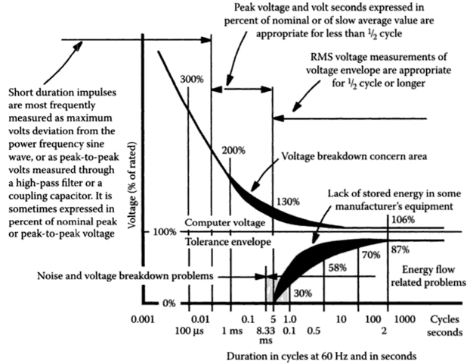A dynamic voltage regulator (DVR) and static synchronous series compensator, or SSSC, are utilized for series voltage sag compensation. A surge protector or simple capacitor or varistor can protect against most overvoltage conditions, while a lightning arrestor protects against severe spikes. Electronic filters can remove harmonics.